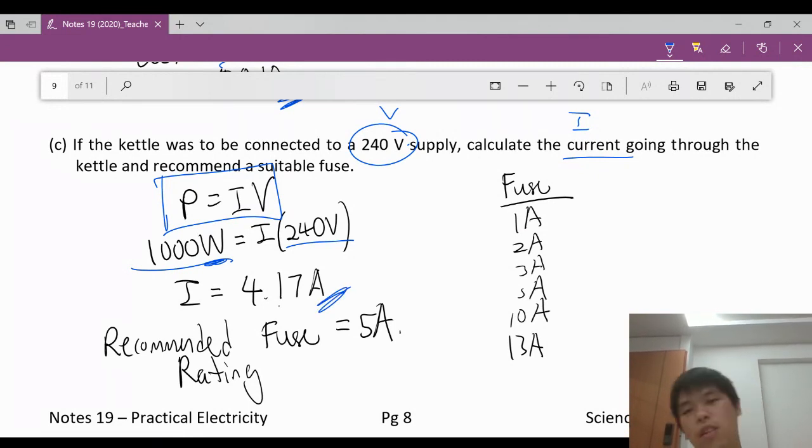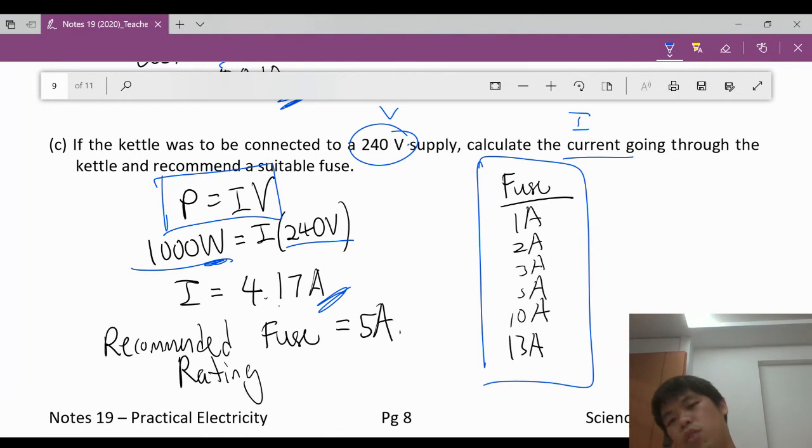What are the fuses that we have? There are only the fuses with the following ratings: 1, 2, 3, 5, 10, 13. We need to be slightly higher than the one that we are in operation here. Slightly higher than 4.17? Only 5 ampere. So, we want the fuse rating to be 5 ampere. Slightly higher than 4.17. So, with that, we will end on the topic of dangers and hazards of electricity.